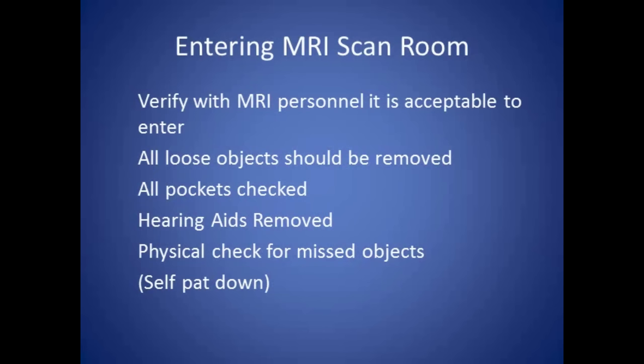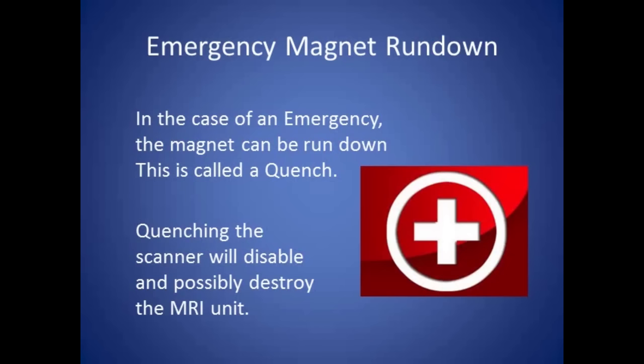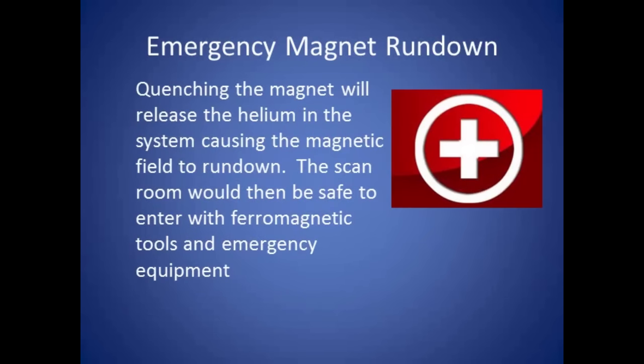In the case of an emergency, the magnet can be run down. This is called a quench. Quenching the scanner will disable and possibly destroy the MRI unit. Quenching the magnet will release the helium in the system. This causes the magnetic field to run down very rapidly. The scan room would then be safe to enter with ferromagnetic tools and emergency equipment. This process may take up to a full minute before the magnetic field drops down to a safe level.